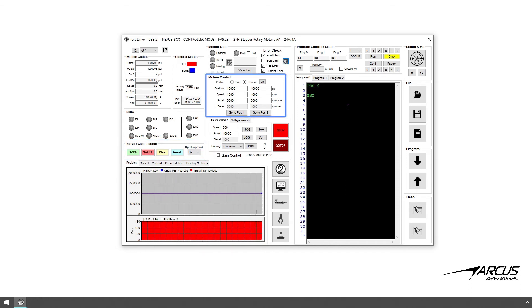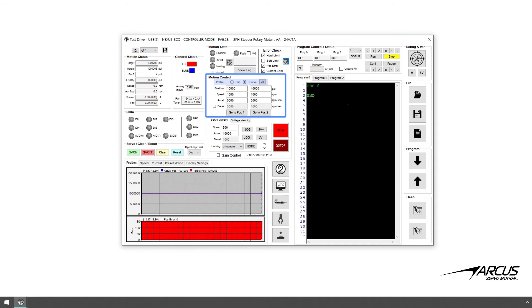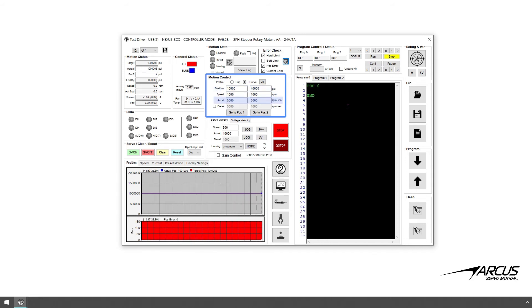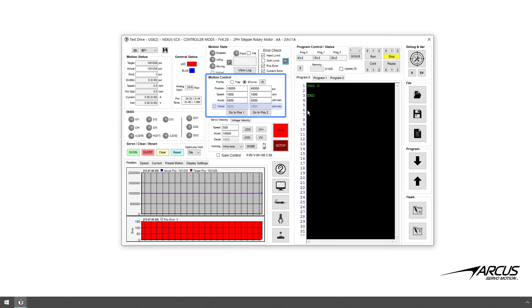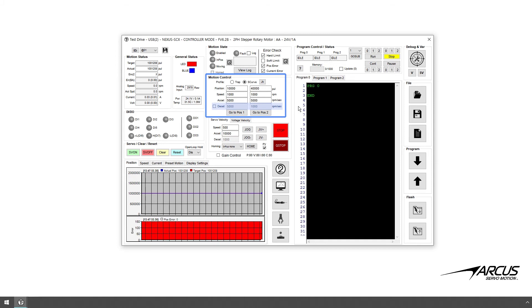Now let's go to the motion control section. At the top there are two profile options: the trapezoidal profile and the S-curve profile. The jerk value for the S-curve profile can also be set. Below the profile selection there are two sets of target position, speed, acceleration, and deceleration values. The decel checkbox is available to enable separate acceleration and deceleration values — if this decel checkbox is not set, acceleration and deceleration will be the same value. There are two buttons, go to position one and go to position two, which are available to test the moves between the two positions.